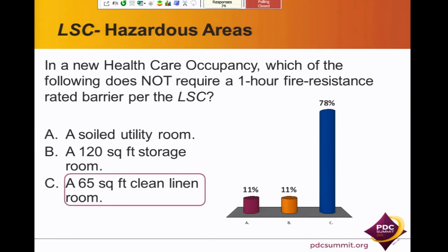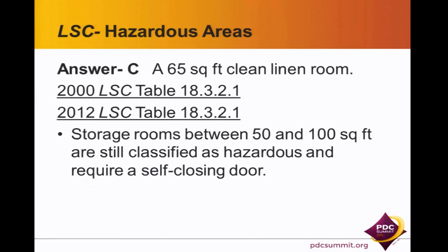C, very good. 65 square foot clean linen room. So storage rooms between 50 and 100 square feet, they're still classified as hazardous. They still require the self-closing door. However, in new construction, they're not required to have that 1 hour.